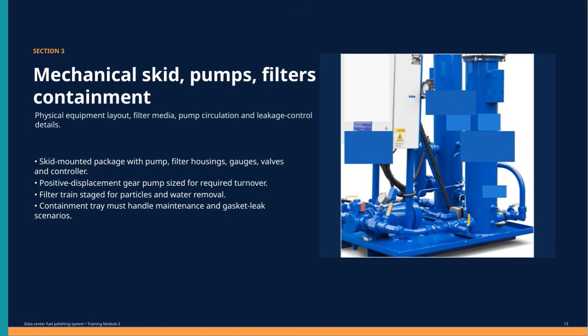The system uses a skid-mounted package that integrates the pump, filter housings, gauges, valves, and a controller into one compact unit. This design simplifies installation and maintenance. At the heart of this setup is a positive displacement gear pump, carefully sized to provide the necessary turnover rate to keep the fuel clean and in optimal condition.